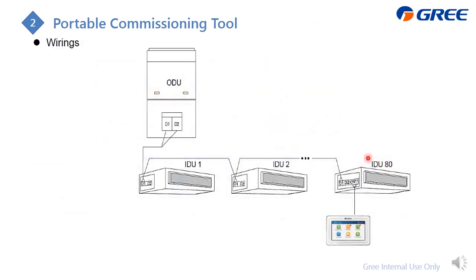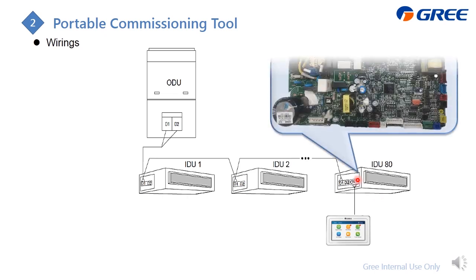As for the wiring of this portable debugger, there is no need for any other device, just a wire from this one, and directly if you choose from the indoor unit, just select any of them, then plug into this CN11. Then for the single system, it is available to do the commissioning, and also you can use this one to set the system parameters like the auto ESP, and also to change the fan speed or control one or multiple indoor units, which is CN11.